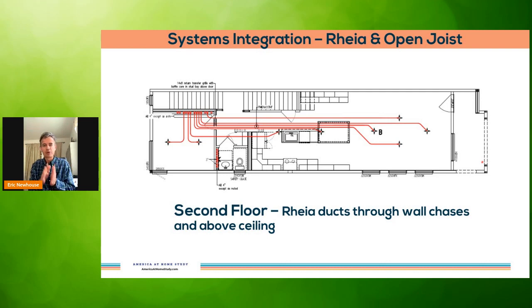The most significant impact on the spatial arrangement from this HVAC approach was on the second floor. The walls along the stair and at the one bathroom were doubled up to be a double 2x4 wall to allow for Rheia ducts through wall chases. Again, the ductwork to the second floor was routed above the ceiling to ceiling diffusers throughout that space.